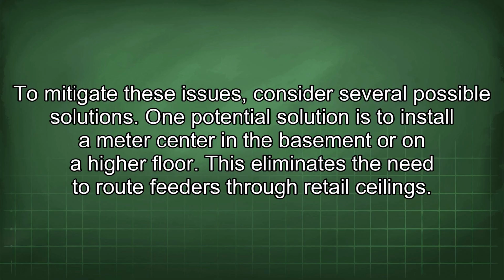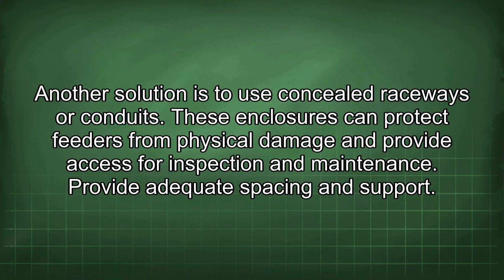One potential solution is to install a meter center in the basement or on a higher floor. This eliminates the need to route feeders through retail ceilings. Another solution is to use concealed raceways or conduits. These enclosures can protect feeders from physical damage and provide access for inspection and maintenance.